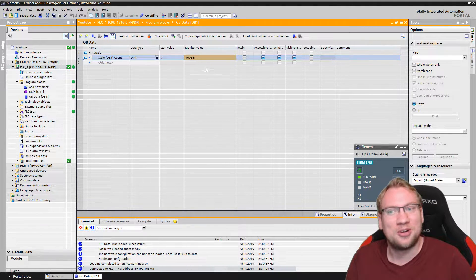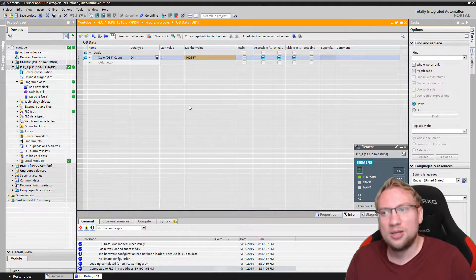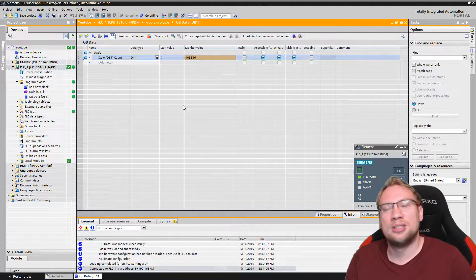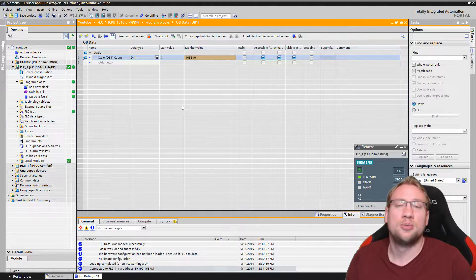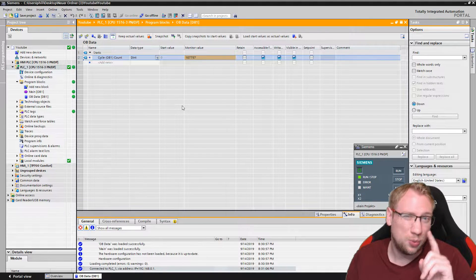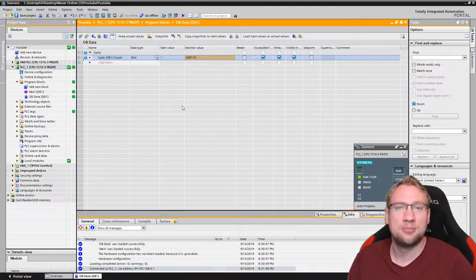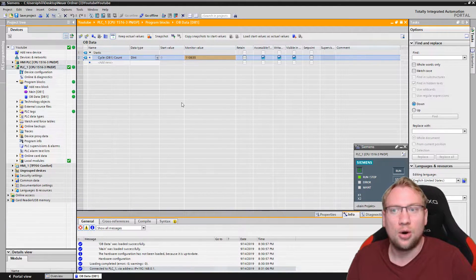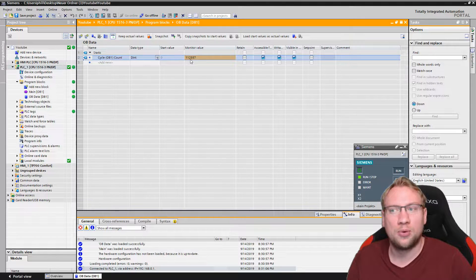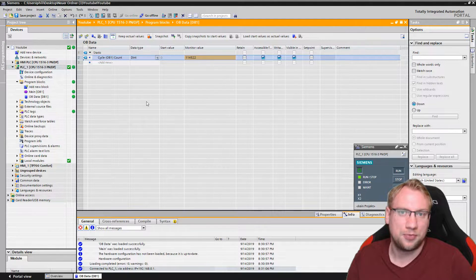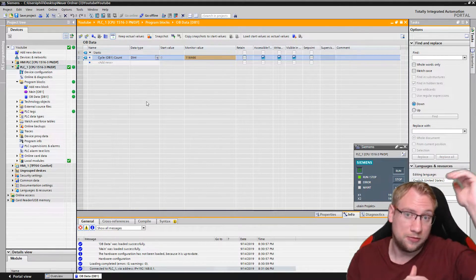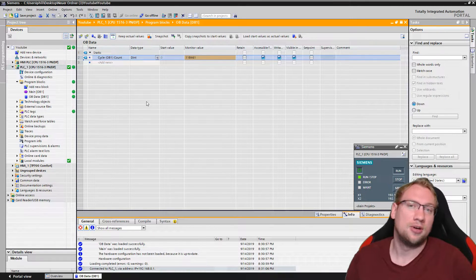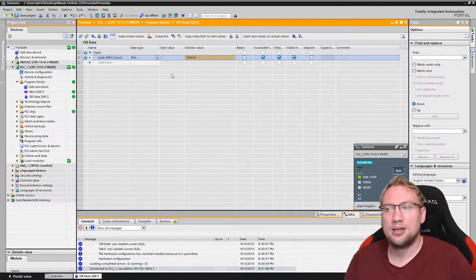Today we're going to talk about the OB100, which is the startup organization block, which is called and executed only one time and exactly at the beginning of our program, even before the cycle starts. So we have OB100, which sits before the cyclic behavior of our PLC starts.